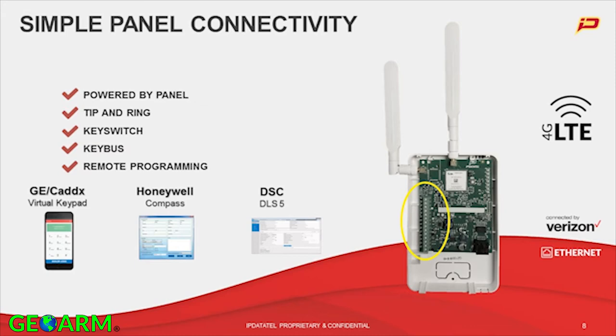There are a couple of different types of connections on this device, which is the universal portion. For GE Caddx, Honeywell, DSC, and GE Concord, all of these provide keypad emulation — they go into the keypad terminals on this device, allowing you to see the full keypad. So if a customer has a Honeywell Vista panel and wants to change a user code, you can do that remotely from your office without running a service call. We also provide key switch arming and disarming — a more basic arm and disarm solution — connecting to the panel on an open zone, allowing you to arm and disarm through a voltage change.